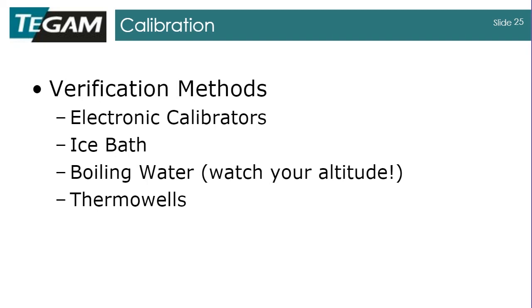Some people are more belt-and-suspenders and want to check both a cold and a hot temperature, using the boiling point of water as the other reference—that's close to many cooking temperatures, so it's convenient. Interestingly, the ice point of water is very consistent, but the boiling point varies with altitude and barometric pressure. So you need to know your altitude and correct for it—a boiling point check in Denver will be different than one in Cleveland.